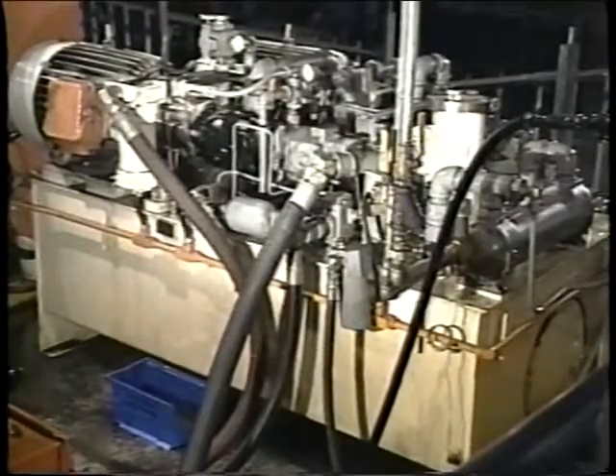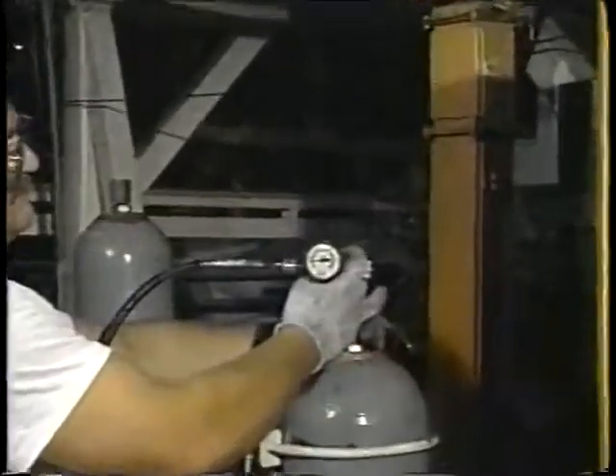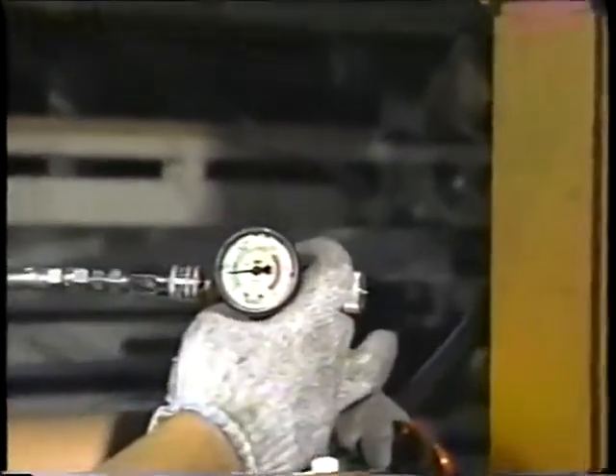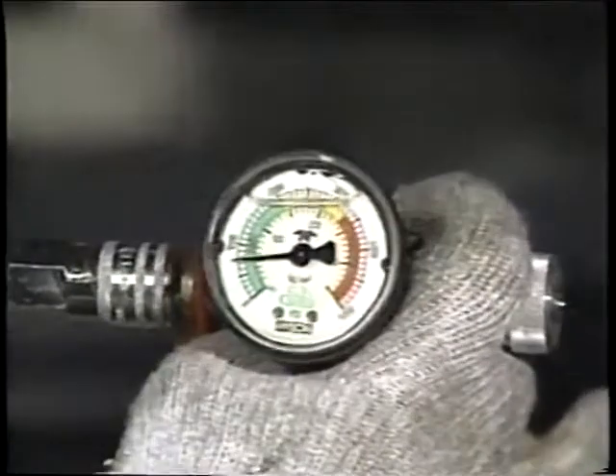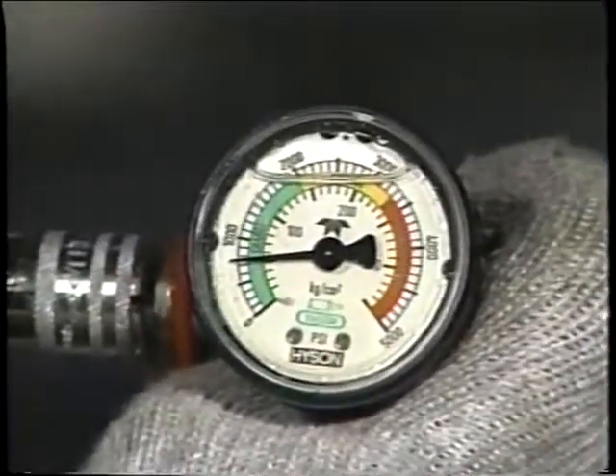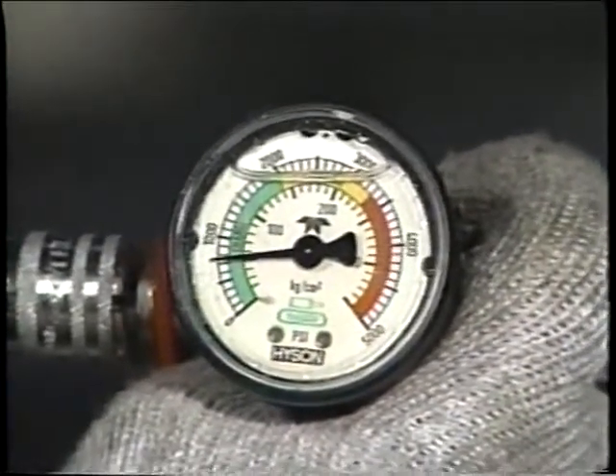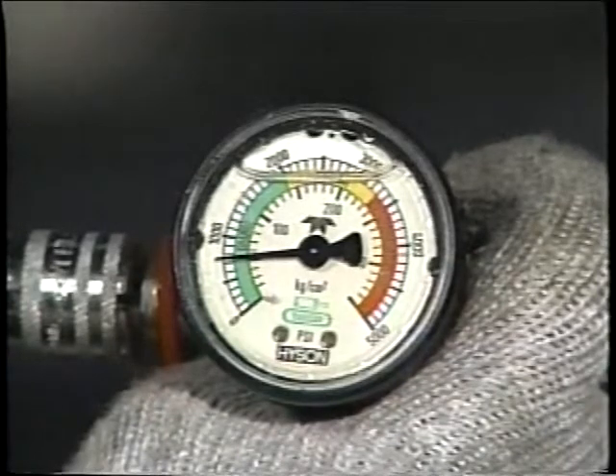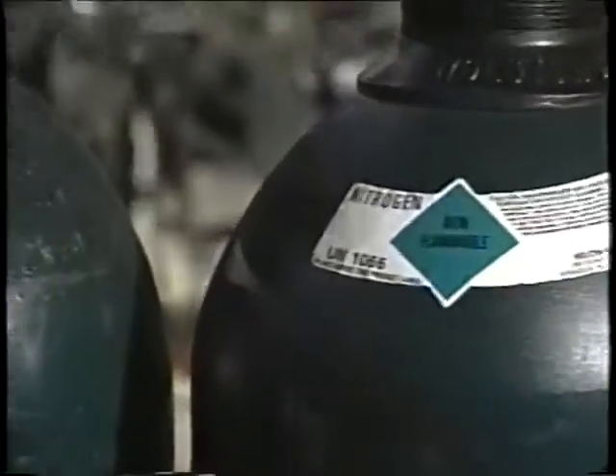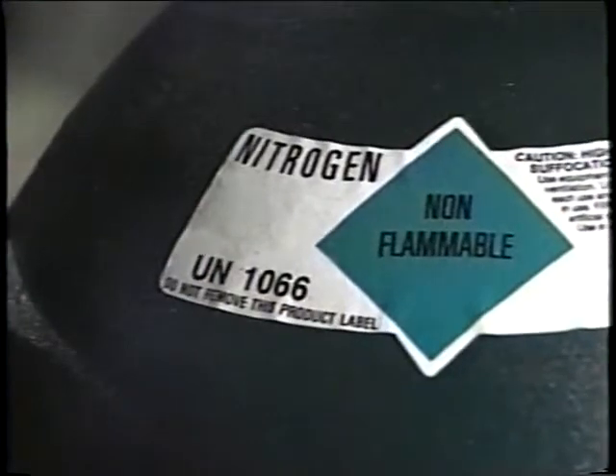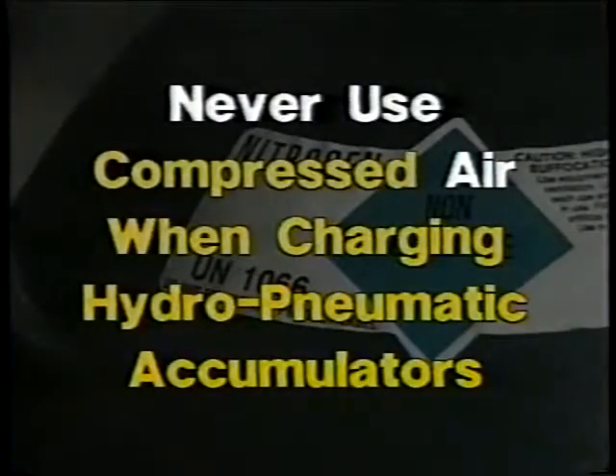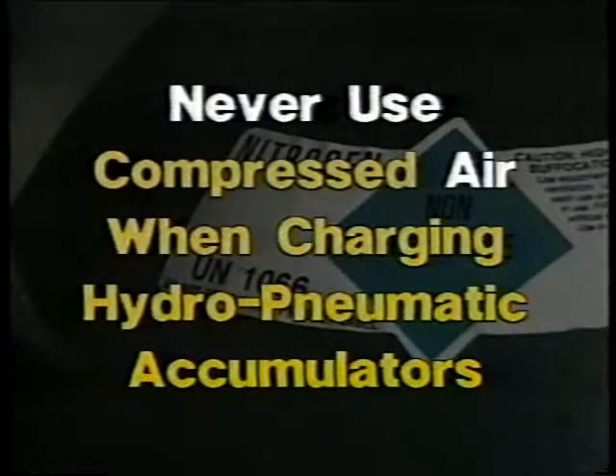Before this type of accumulator is used it must be pre-charged or filled up with compressed gas. If the proper pre-charge is not applied and maintained, the accumulator will not operate correctly. Only dry nitrogen should be used as a charging gas — never use compressed air because it may create an explosive vapor of air and oil.